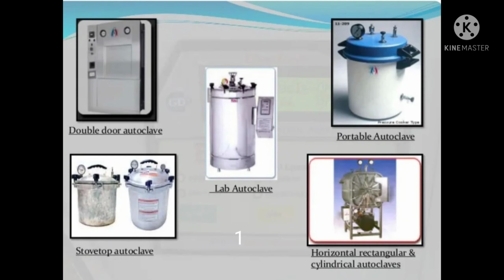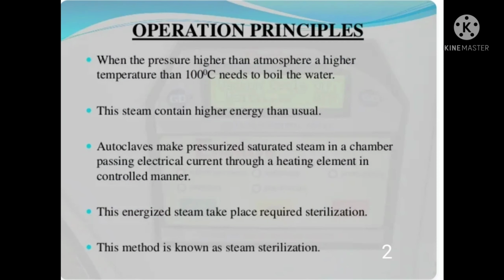Autoclaving is one of the cheapest and time-tested methods of sterilization. There are different options available in the commercial market for the autoclave. An autoclave is basically a metal cylindrical drum used for creating steam under pressure. It has a double wall, it has an inlet and outlet, and a pressure release valve. There are different types of autoclave like horizontal autoclave and vertical autoclave. Some modern autoclaves like the B class autoclave and class S are also available.